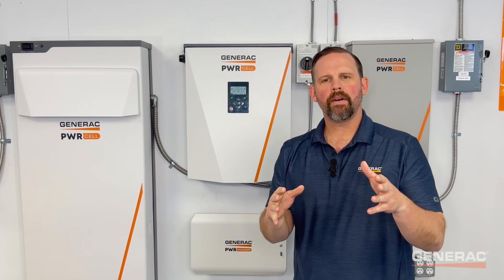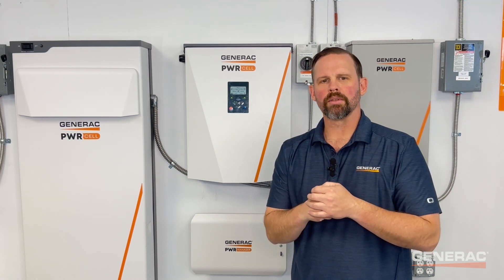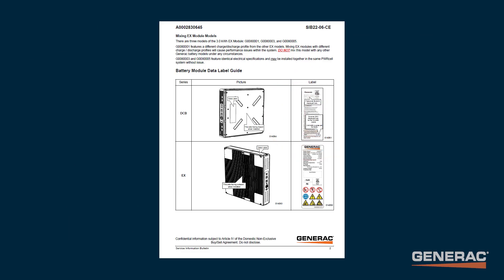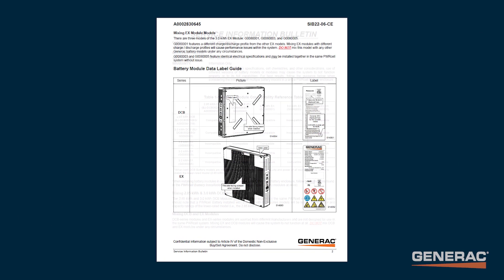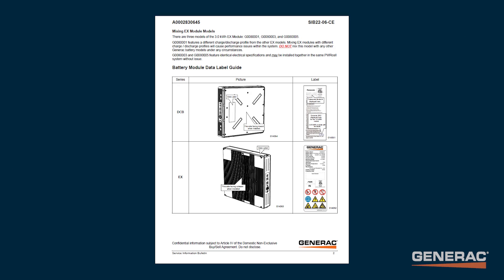To troubleshoot, first verify the battery modules are compatible models. Check the model number on the nameplate of the battery modules. If they're not the same model, refer to SIB-2206CE — mixing EX module models with PWRcell — to verify module compatibility.